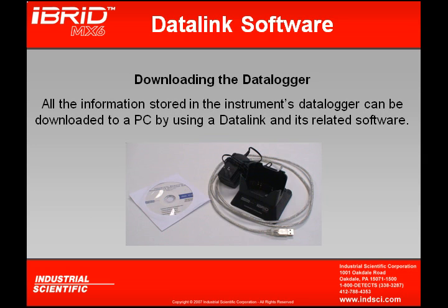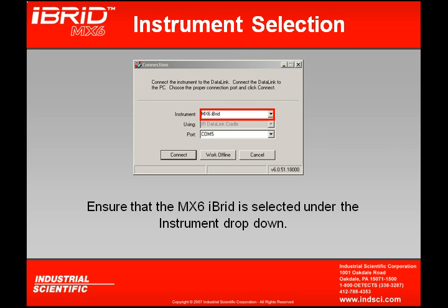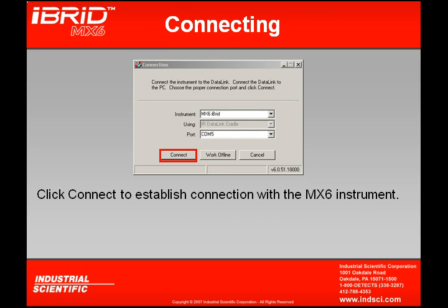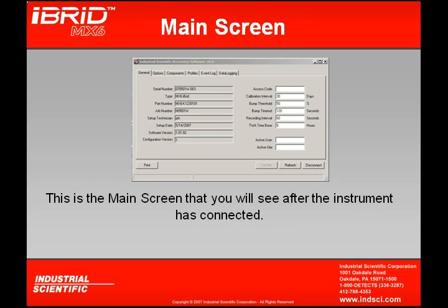Not only can I data log information and view it on the instrument's display, but I can also download that same information to a PC using something called a data link software kit. Once my software is installed, I'll see the following screens during my downloading procedure. Before you download, you need to ensure that MX6 iBrid is selected as your option under Instruments, and that you have the correct COM port selected. Once the MX-6 instrument is in its cradle, by clicking Connect, I'll be able to communicate with the instrument. Once communication is established, a screen will appear with six different tabs.